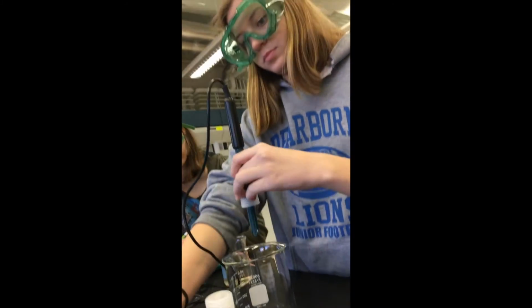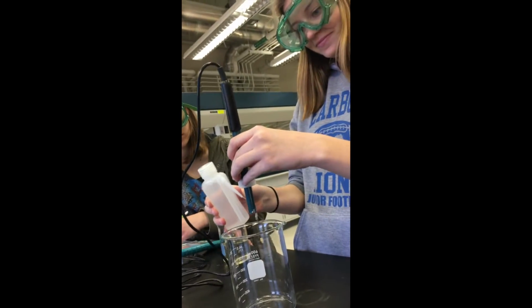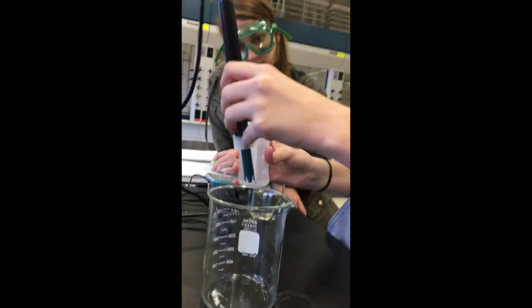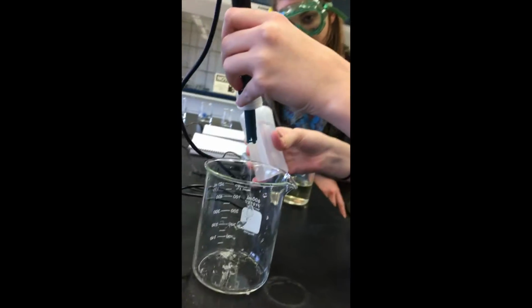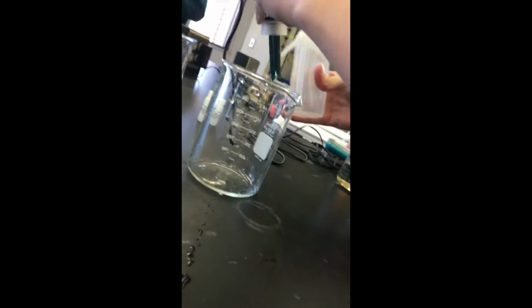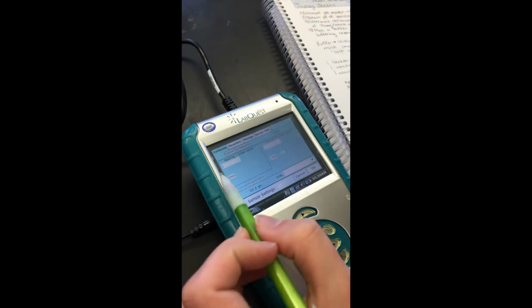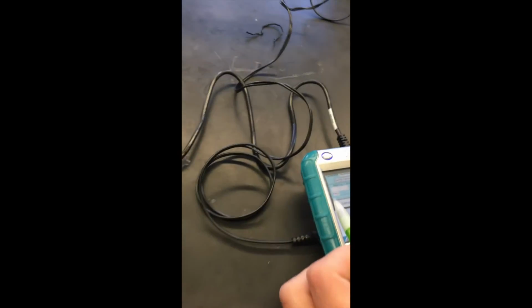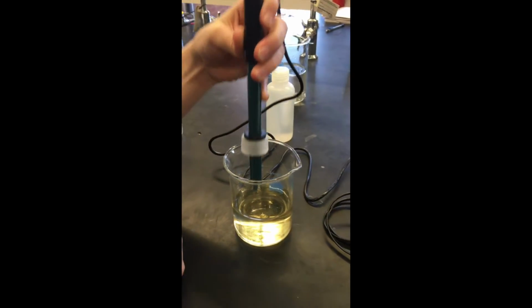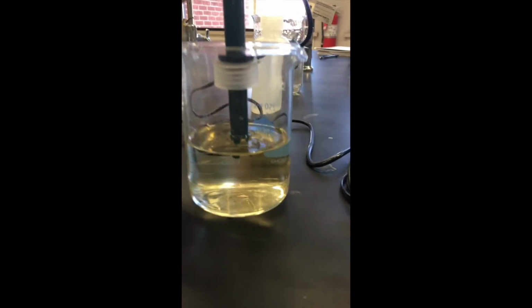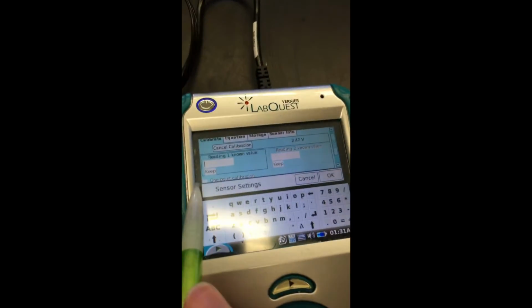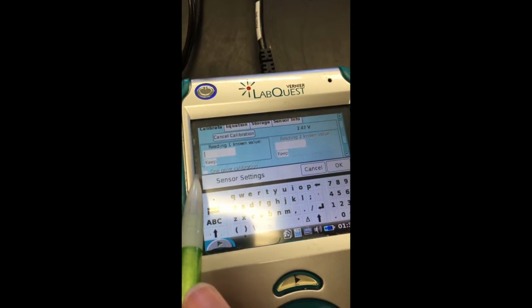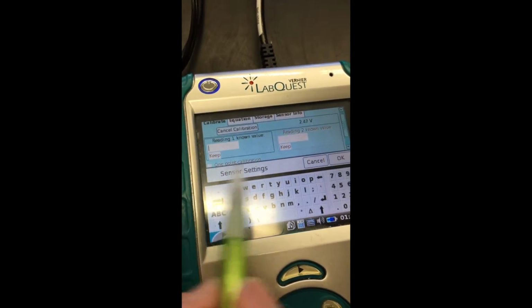In order to use a pH meter, you must first prep it. The first step to prepping a pH meter is to clean the probe with distilled water to ensure proper cleanliness for a more accurate reading. Second, you must calibrate your pH meter. Press Calibrate now, and then place the probe into the buffer 4 and gently swirl it until you get a stable voltage reading. Press 4 and then press Keep to store the recorded voltage of the buffer 4.